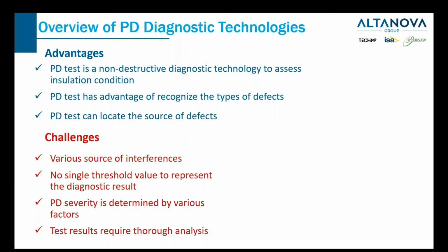The second challenge is when we do the PD test and try to make sense of and get value from the result, we always want to know what is good, what is bad. Such as the leakage current test, apparently if leakage current is higher than a certain threshold value, that equipment is not in good condition. With PD test, we are trying to use the same criteria, but unfortunately it doesn't work. There's no single threshold value to present the diagnostic result. We cannot say this equipment with 100 millivolt discharge or 50 picocoulomb discharge is bad, or that device with 20 picocoulomb discharge is good. So the testing result is more complicated than other testing technologies. We're going to talk a little bit about the details on that.